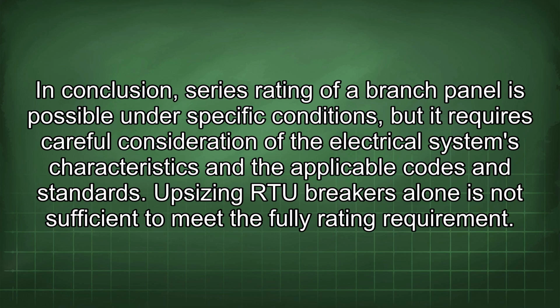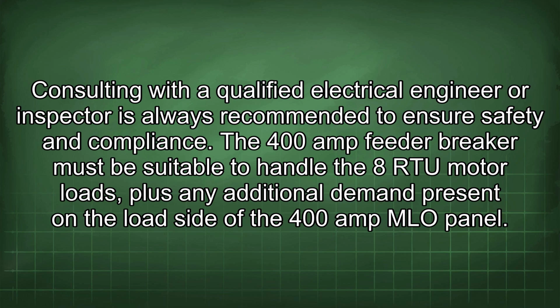Upsizing RTU breakers alone is not sufficient to meet the series rating requirement. Consulting with a qualified electrical engineer or inspector is always recommended to ensure safety and compliance. The 400 amp feeder breaker must be suitable to handle the 8 RTU motor loads plus any additional demand present on the load side of the 400 amp MLO panel.